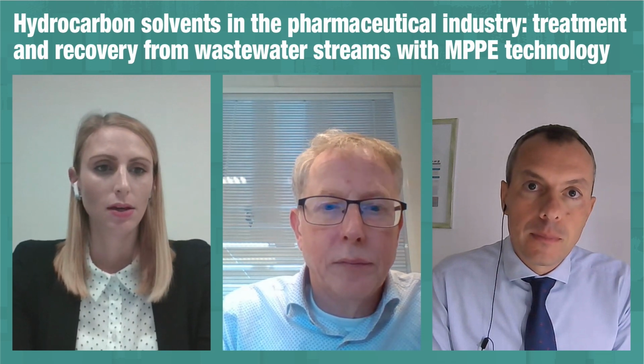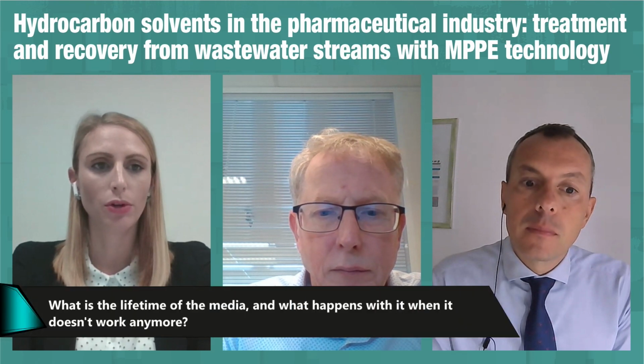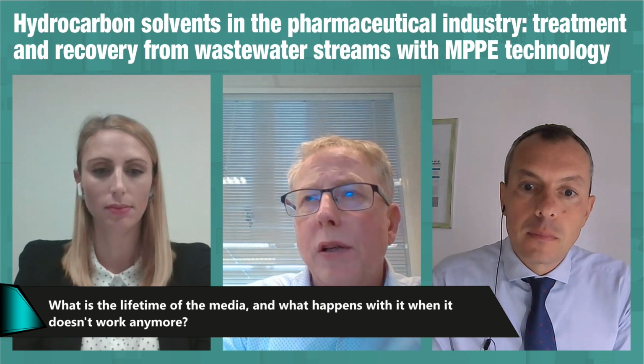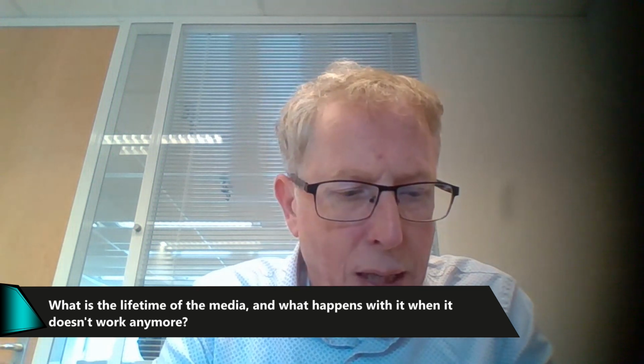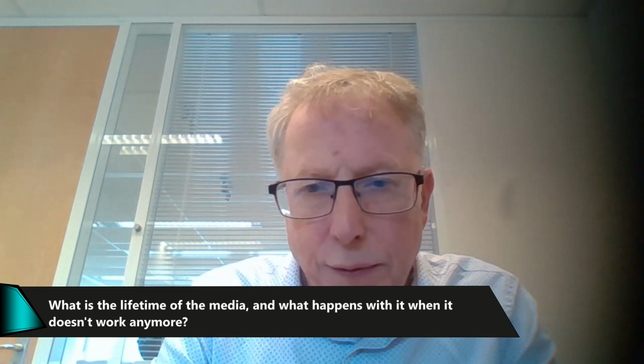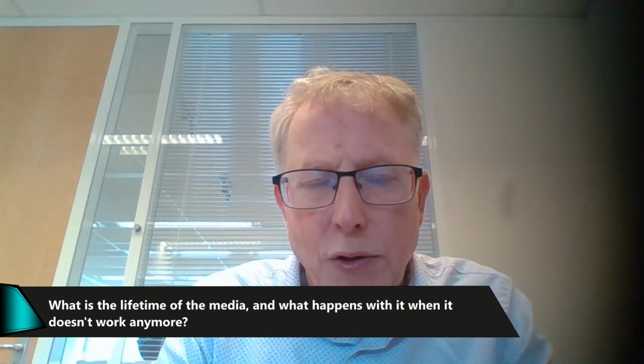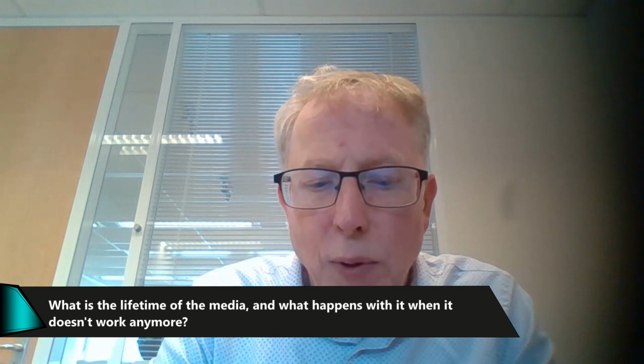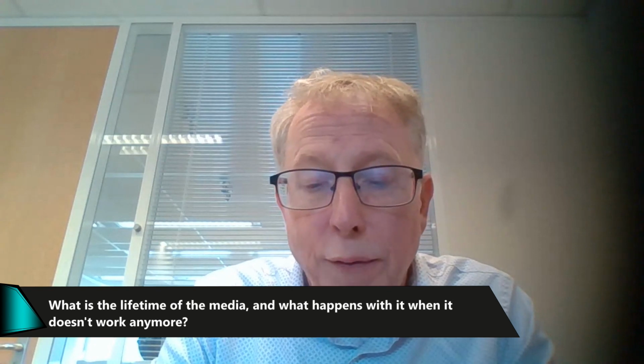What is the lifetime of the media and what happens with it when it doesn't work anymore? Jerome, you can cover that. Yeah, so that's a good question. The different types of media we are using, basically we always take it back when its lifetime has ended, and the lifetime depends very much on the type of application. If you look at some of our oil and gas applications where we are treating relatively clean streams, then the maximum lifetime we ever observed was 7 years. But typically, I would say it's between 2 and 4 years.